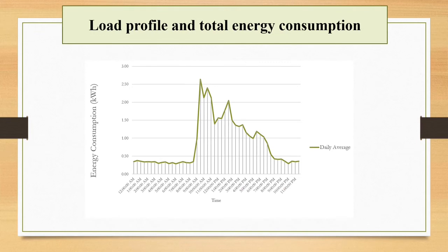The figure shows a line chart of average daily energy consumption at the premise. The percentage of the base load is 16.88%. The base load contributes from 12 am until 9 am. There is a consumption between the time even the restaurant does not operate because there are few electrical appliances that run 24 hours, such as refrigerator and freezer. The peak consumption is starting after 9 am since the shop operates at 10 am.